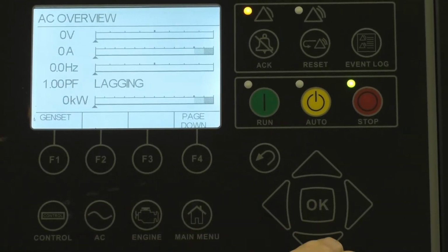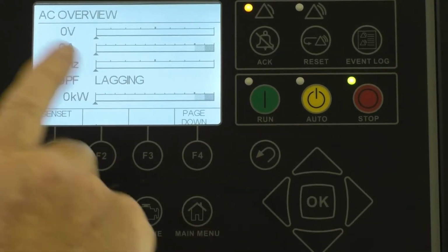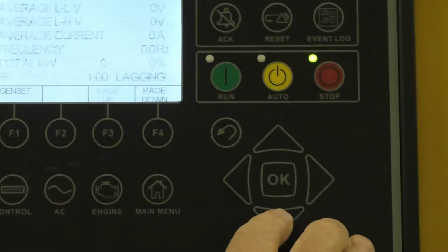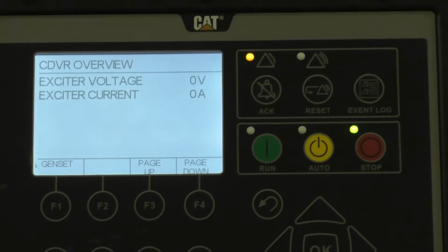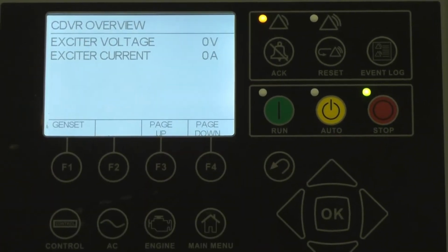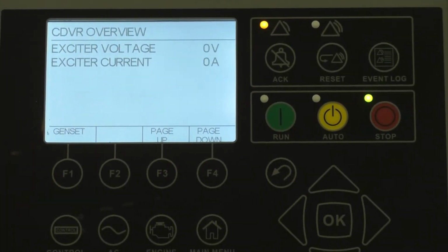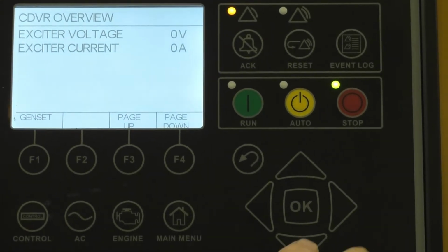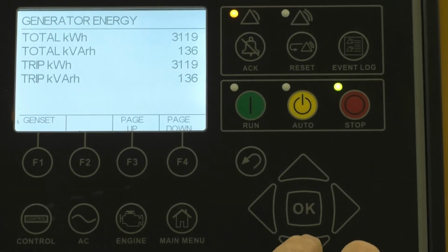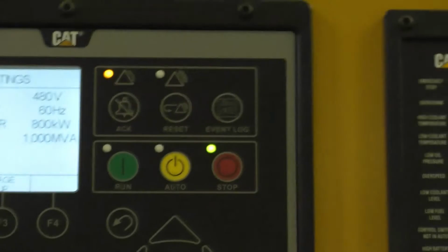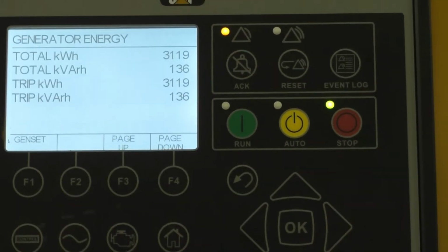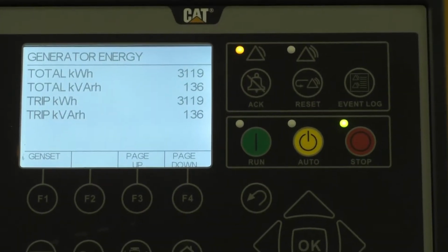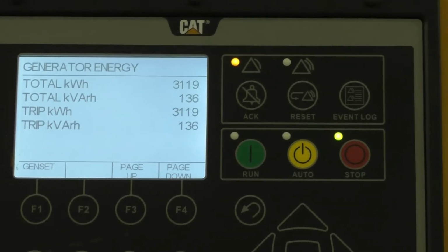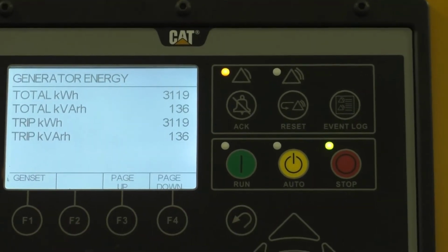Now we go to the AC side. It starts out at this screen, and it's a graph, and it gives you numbers, but you can look at load. You can also break it down individually to anything you want. You can see what the exciter's doing from the voltage regulator to the generator. It's a good way to see the status of your generator. Something might be going wrong or whatever. And then it'll give you counters for how many kW hours, kVAR hours, and so on that it's running. That's the numbers so far.